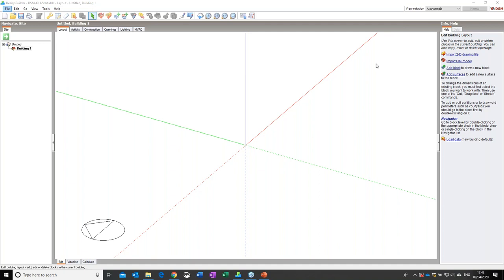To set the context, we'll assume this is an early-stage model where we're testing initial design data to check performance ahead of any regulatory submissions. The NCM location is set to London with the London CIBSE test reference year weather file used for the DSM simulation. If you have a BIM model or a model created in another tool you can import it in gbXML form into Design Builder; you can also import floor plans from CAD plans or other formats including PDF. Today I'm going to create a fairly simple representative layout of a student accommodation block freehand.